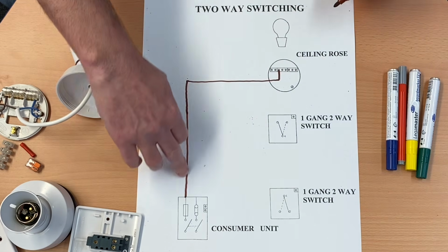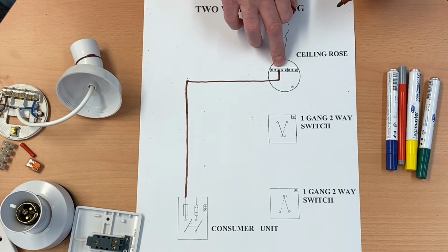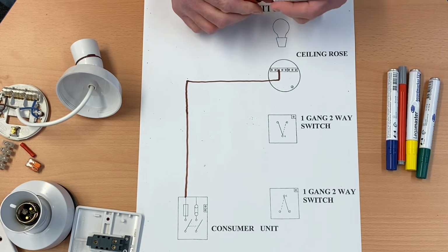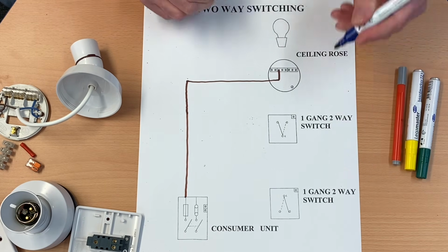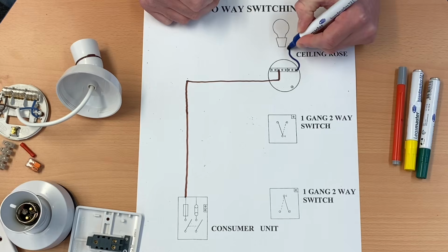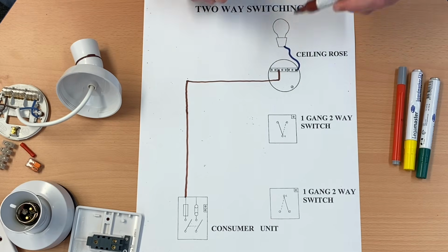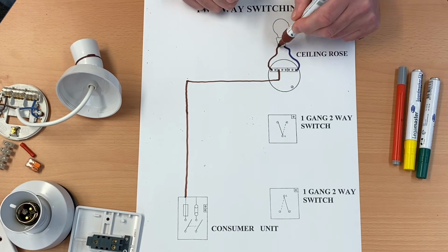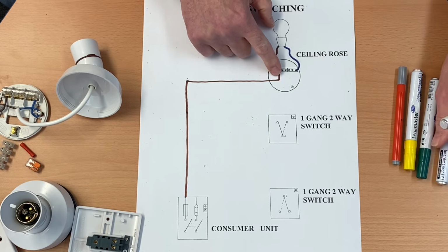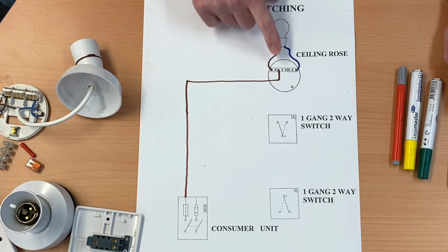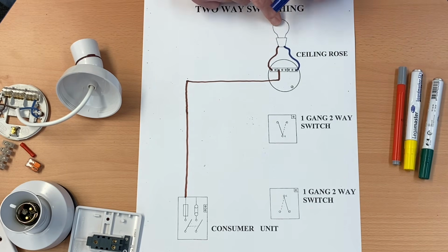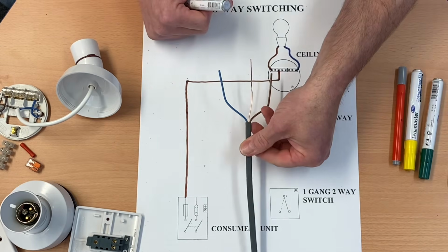So that's brought our permanent line connection into the block of three in the center, which is loop. These are not connected to the lamp. Remembering the lamp itself will have a neutral on one side and a switching line on the other side, and we won't want a permanent connection to the line to be across the lamp because the lamp would illuminate all the time. So the cable is a PVC twin and CPC.